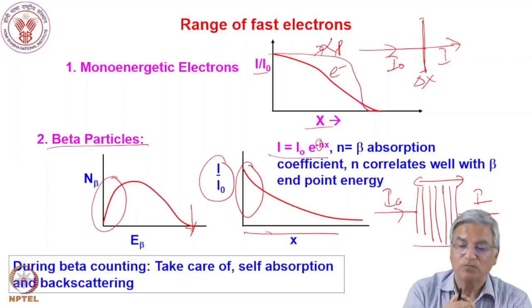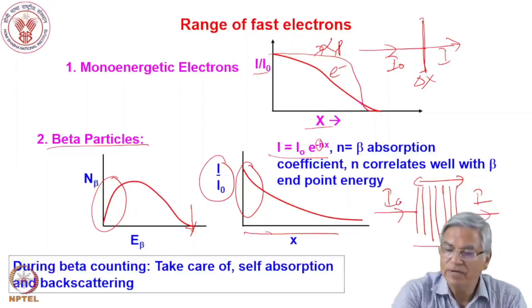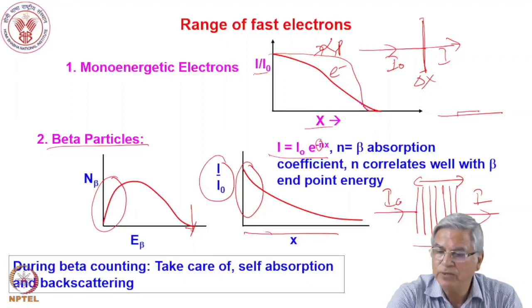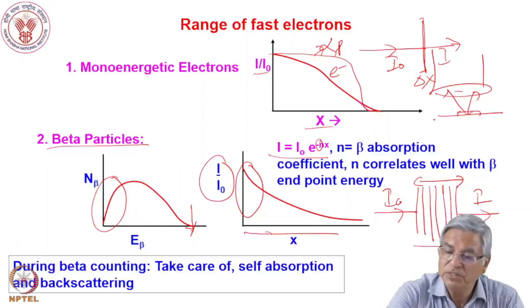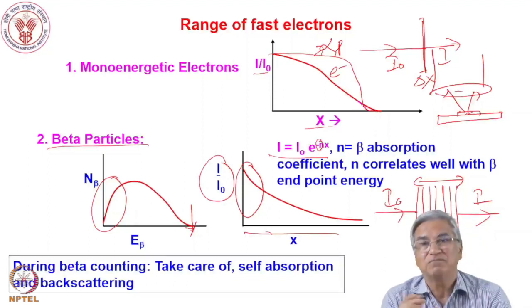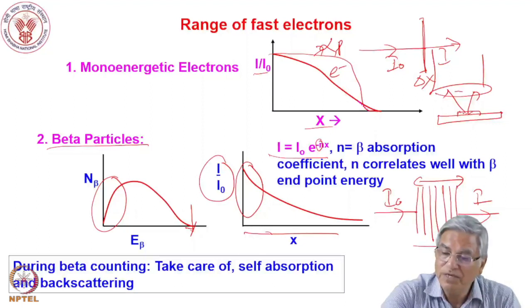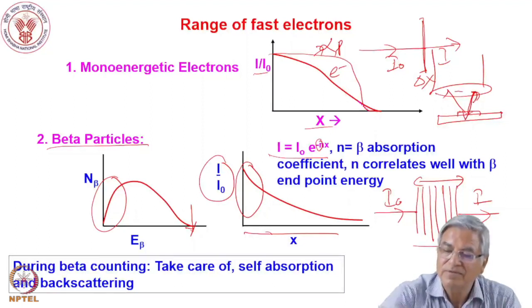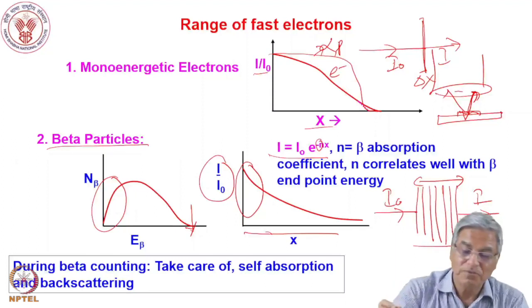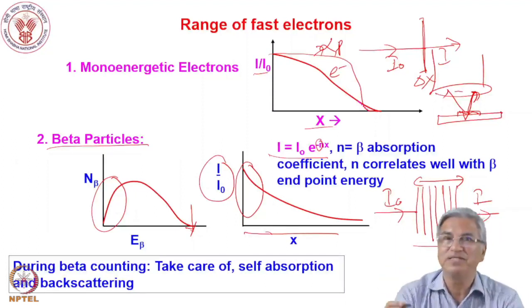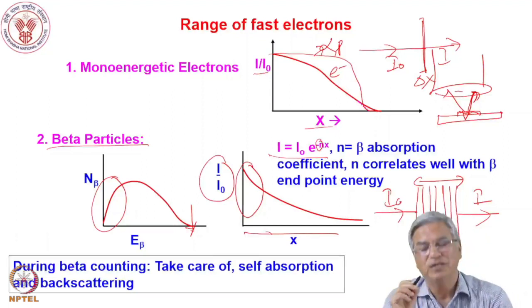Beta counting requires care regarding attenuation. If you have a sample on a plate in a detector, the beta particles travel from sample to detector. If the backing material is high-Z — like lead, stainless steel, or tantalum — there will be backscattering. Additionally, there is self-absorption in the precipitate, and if the material is high-Z, Bremsstrahlung can also occur. Therefore, when doing beta counting, one must not use high-Z backing material.